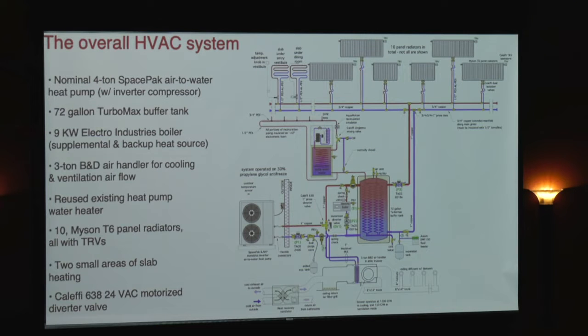Now, one of the things we could have done here, and we thought about it, is home-run all that PEX tubing back to a manifold, you know, a typical radiant floor manifold. I'll call it a compact manifold. That would have required a lot of tubing to bring basically 2 floor heating circuits and 10 panel radiators all back to one manifold station. A lot of tubing and a lot of time drilling holes through floor joists.